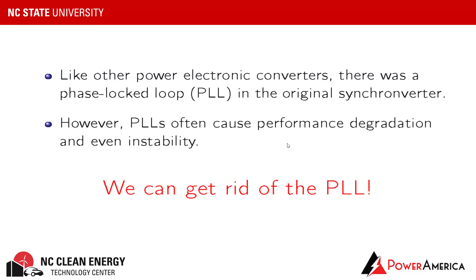Okay, and this slide shows you the self-synchronized synchronous machine without the phase lock loop. We have the self-synchronization mechanism embedded into the system, the VSM. The changes we need to make are introducing a PI controller here, so that we can achieve synchronization before we connect the VSM to the grid. And another important change is to introduce a virtual current, so that we are able to achieve synchronization between the generated voltage E and the grid voltage VG.